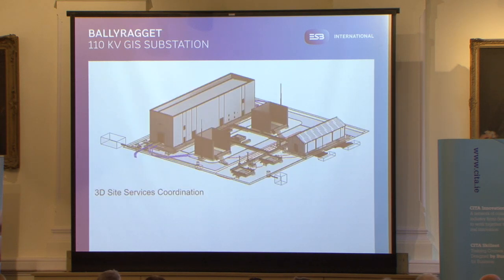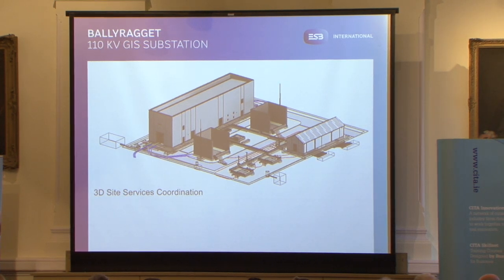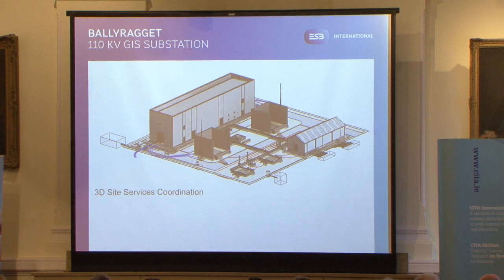This here is the other end of that project — Ballyragget in Kilkenny. You can see the 110 kV bays for transformers and a 38 kV station. The key feature here is that it's a fully coordinated, geolocated site. We geolocated the actual site plan using mapping, then pushed all the coordinates back into the other Revit files — the 110 kV, the bays, and the 38 kV — so everything is geolocated automatically after that.